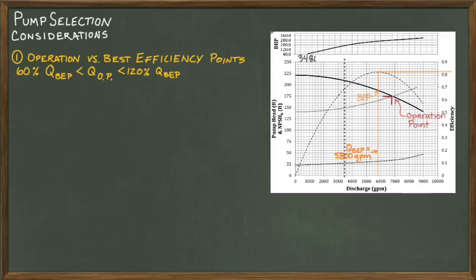So the operating point should be between 3480 gallons per minute and 6960 gallons per minute. In this example, our operating point is at 6800 gallons per minute, so we are good with this parameter.